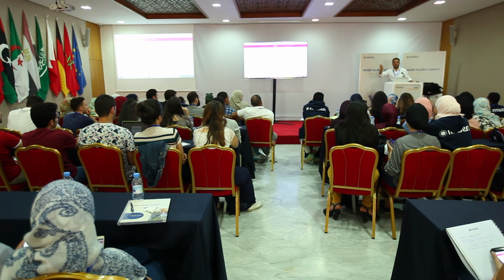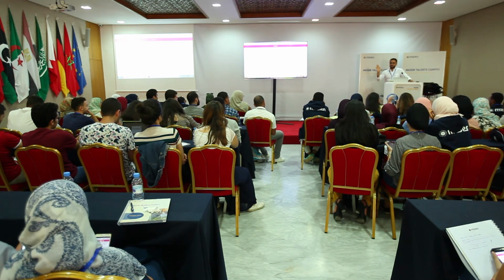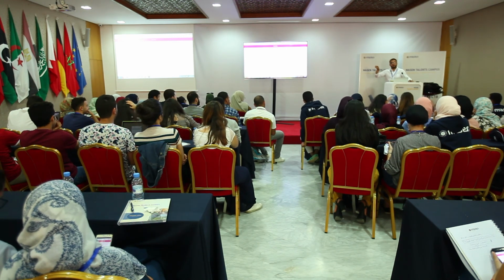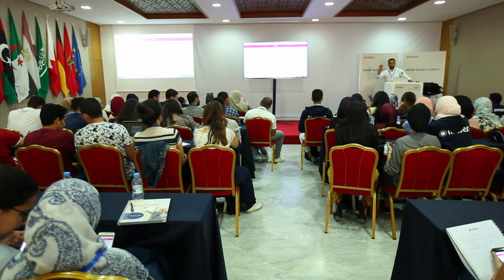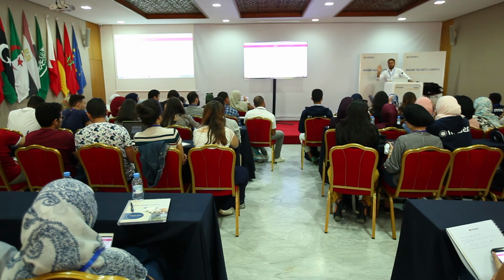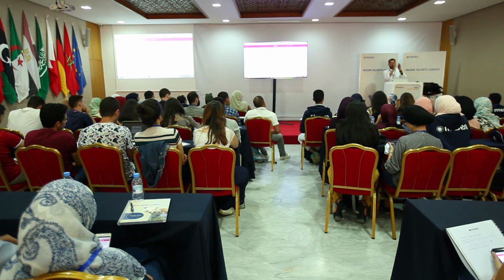This is not the same as if you were paid like this, with 2 peaks, one early in the morning, one early in the afternoon, and you're also paid in the evening, lower, but you're paid. Here, an optimum would be something with 14 hours of storage and a very large field. And here, again, it's a combination of both. In this last case you're not paid in the evening, and you're paid the same all the time, so you just want to operate in the sun hours. That says add no storage, or only enough storage so that you can operate the plant. But that depends on the way you are paid, the revenue streams and so on.